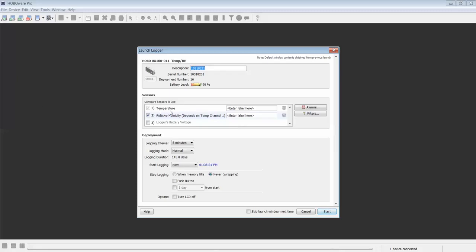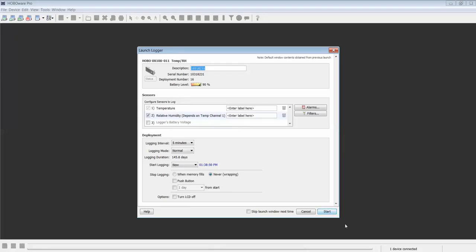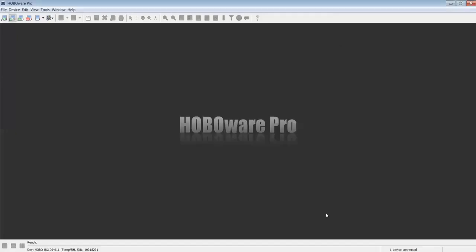Configure this logger for the sensors you want enabled, your logging interval, your logging mode, and how you would like it to start logging. This configuration will be put into all subsequent loggers of the same model number as they are connected with the USB cable. Click Start.